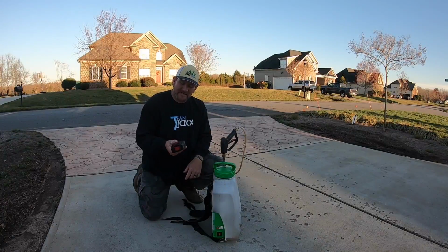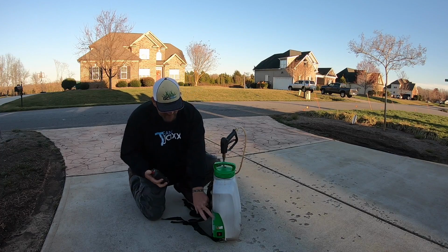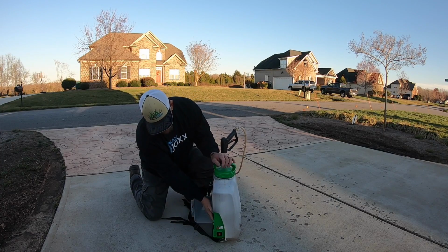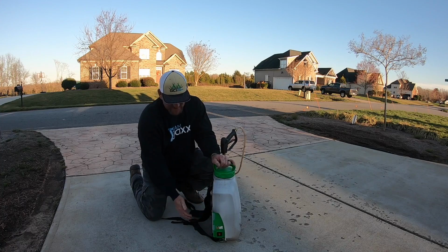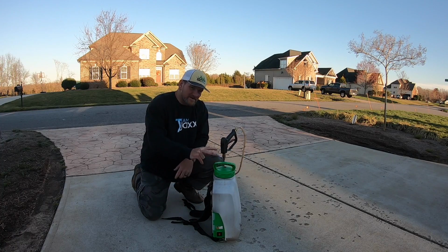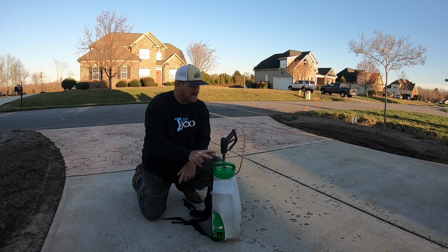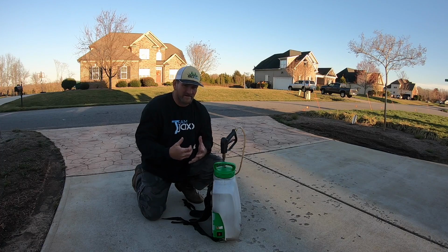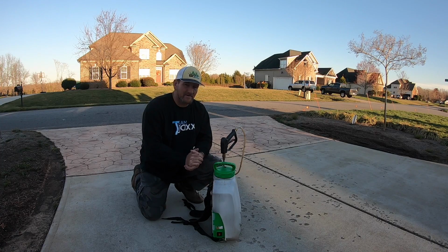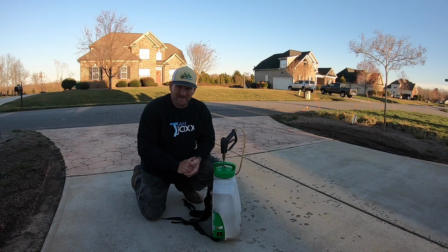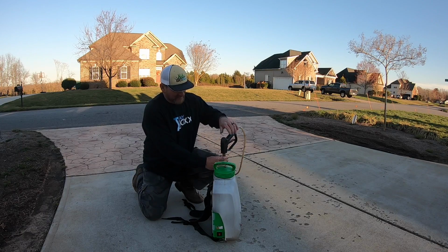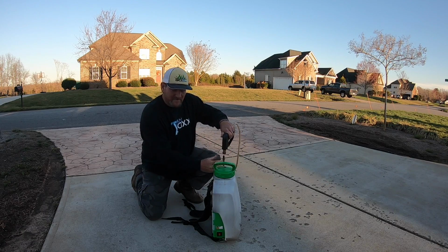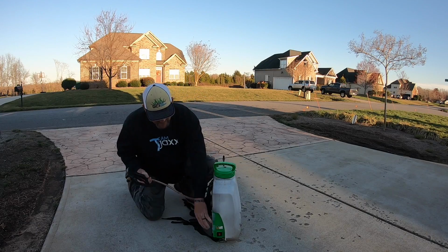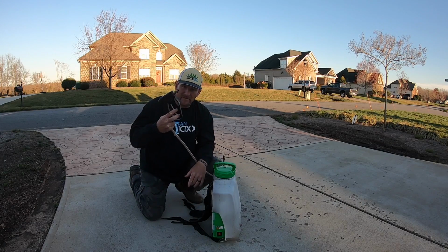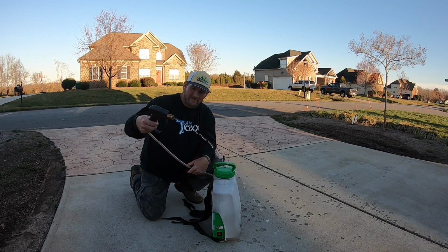The first thing I'm going to do is make sure my battery's charged. Pop the battery in, shut the door. I'm only using water - that's very important, don't calibrate with products or anything like that. Only use water, and practice 2 or 3 times until you get really good at it. I'm going to pop loose my quick connect, get my handle, turn my pump on, and prime it.